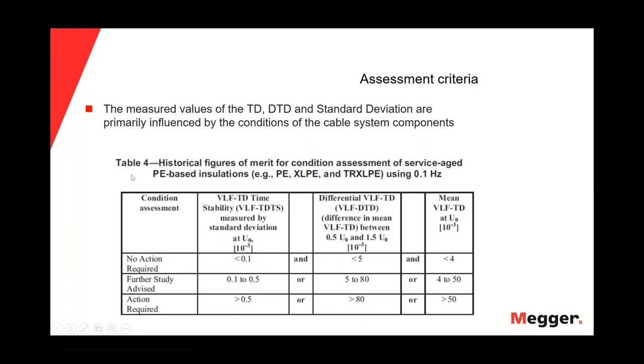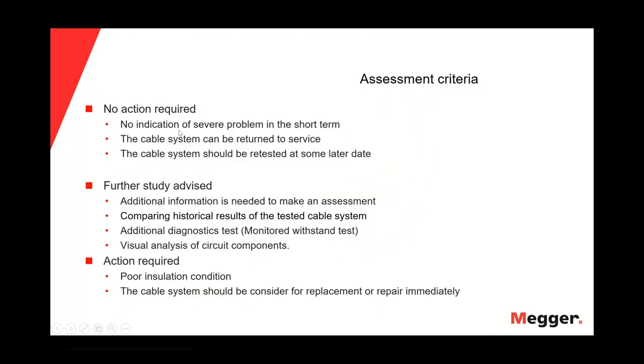In this case, we are seeing table number 4 for PE and XLPE cables. The condition assessment that we can get is: no action required, further study advised, and action required. No action required means that there is no indication of a severe problem in the short term. That means that the cable system can be returned to service, and it should be retested at some later date. Maybe in 4 years we can do the tan delta test one more time, if in the first measurement we get a no action required result.